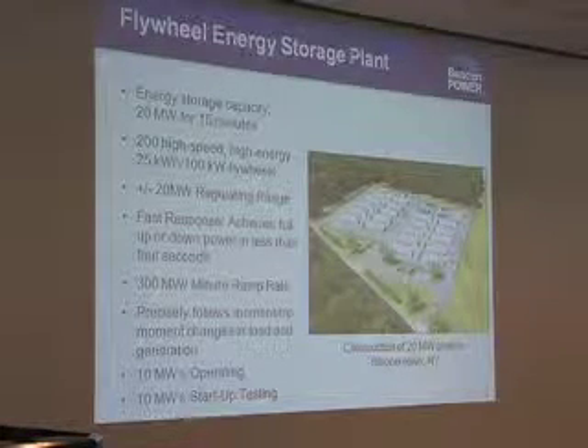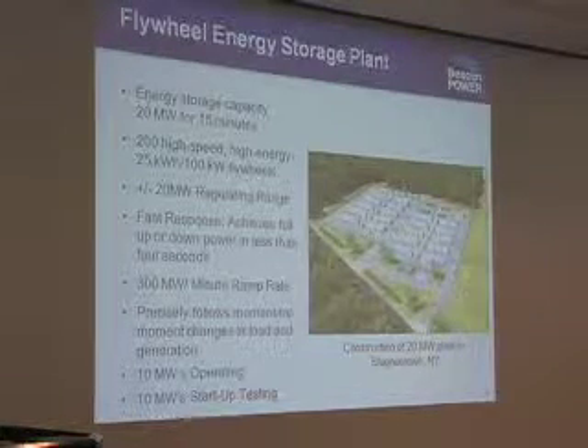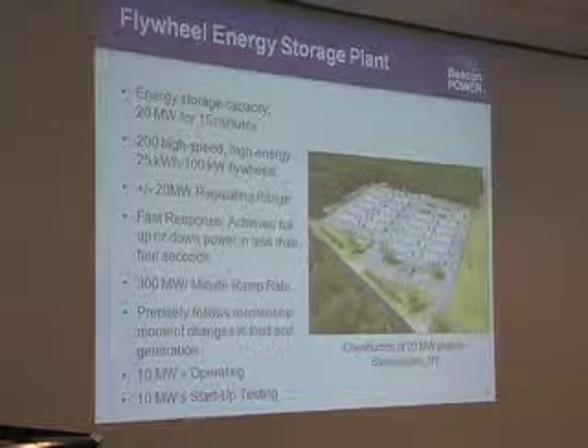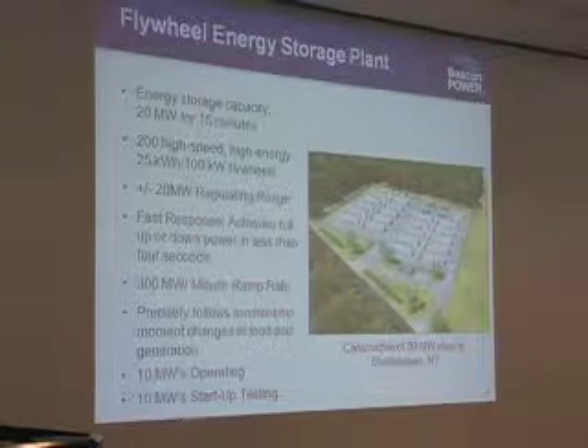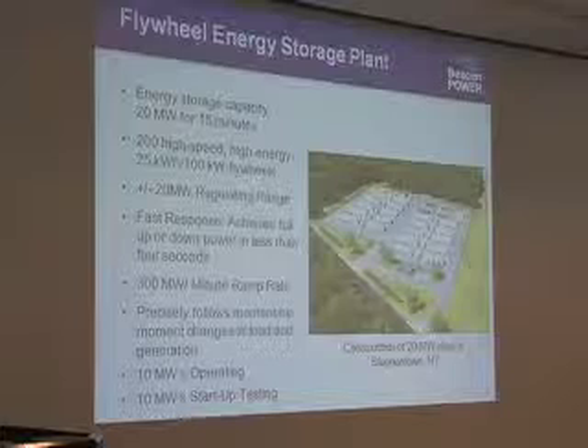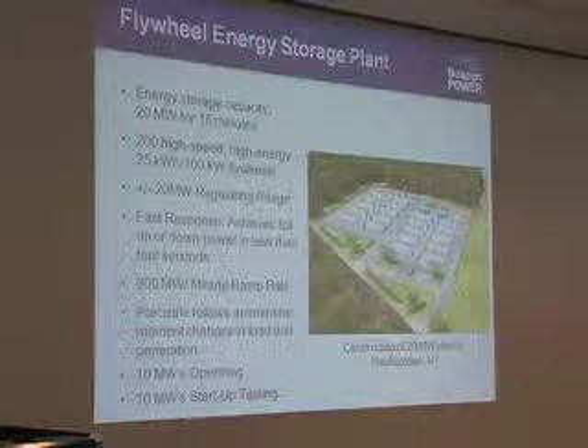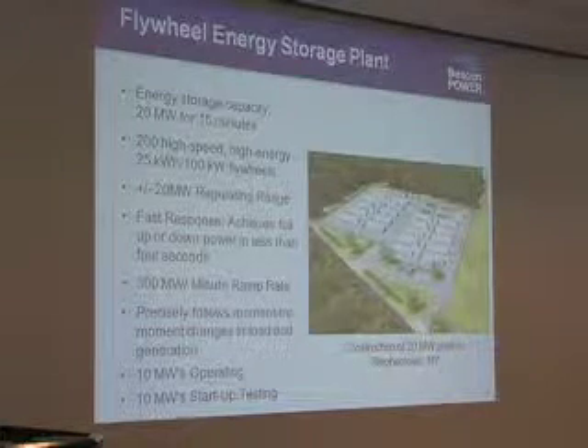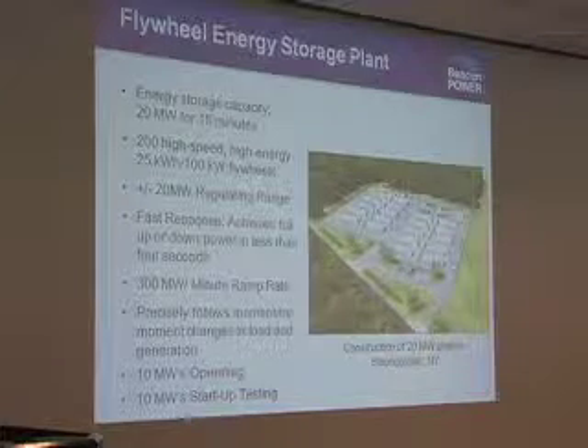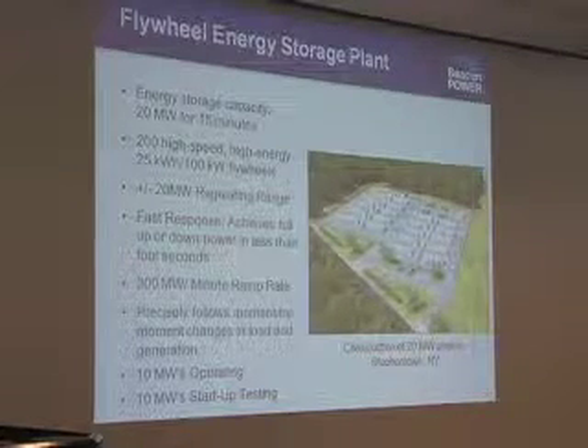So for frequency regulation, it actually provides a load, and like I said, it can react instantaneously. 300 megawatt per minute ramp rate, so obviously it can provide an awful lot of support. And it really does - as soon as we get a signal from the ISO, the dispatch, it adjusts instantaneously.